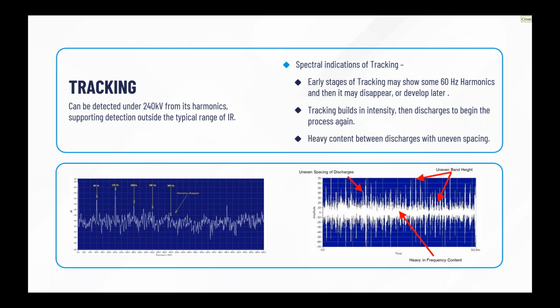If we look at the event over time, we will have both positive and negative discharges, much more aggressive, uneven band heights, uneven spacing. It's just a much more aggressive image. So that's where, if you're not sure if it's corona or tracking that you're hearing, when we look at the event over time, it becomes very, very clear. The tracking is always going to be an aggressive sample in the event.